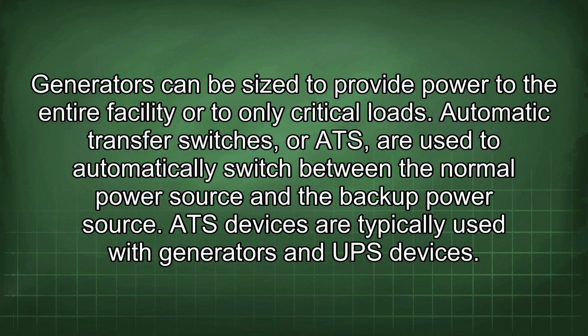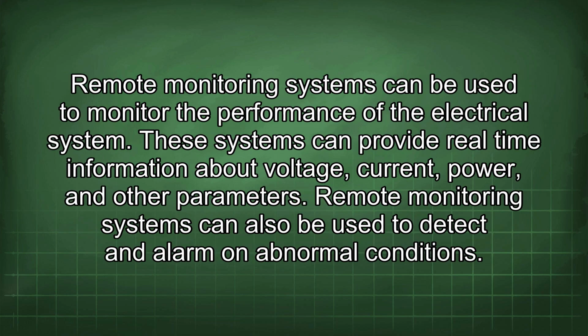Automatic transfer switches, or ATS, are used to automatically switch between the normal power source and the backup power source. ATS devices are typically used with generators and UPS devices. Remote monitoring systems can be used to monitor the performance of the electrical system. These systems can provide real-time information about voltage, current, power, and other parameters. Remote monitoring systems can also be used to detect and alarm on abnormal conditions.